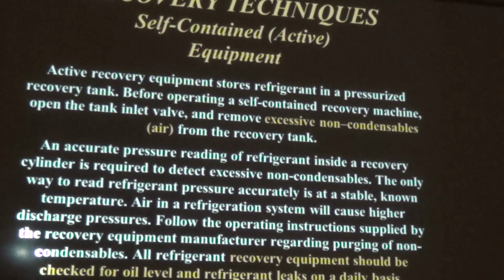So if you've got R22 in a recovery tank, and let's say it's 40 degrees, we'll make it easy, then the pressure of that cylinder should be 69 pounds. If you're getting a different reading, then it means that too much air has gotten into that system.